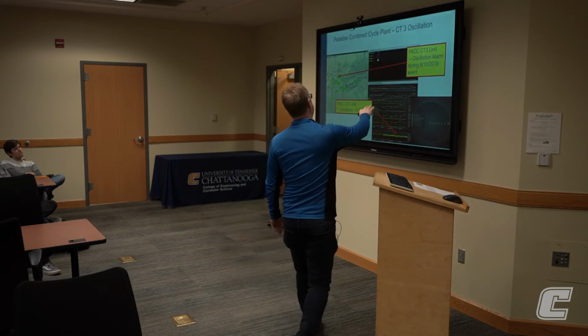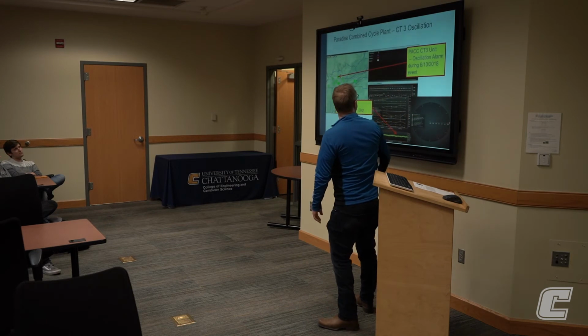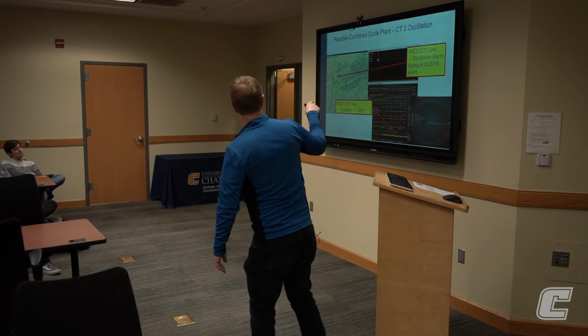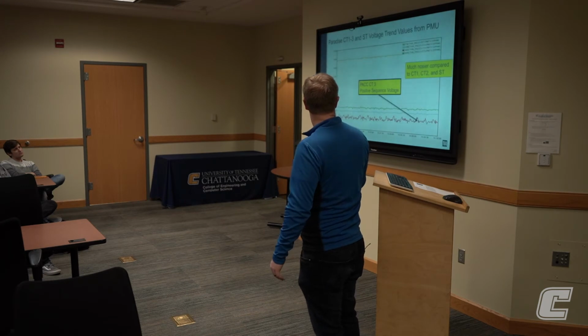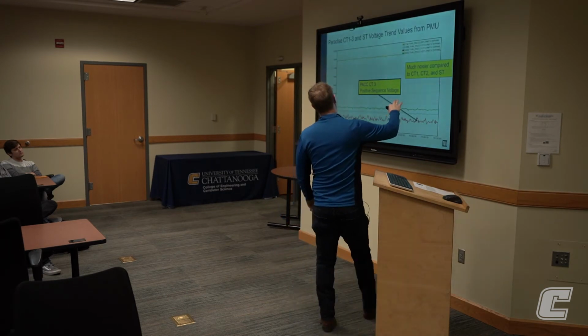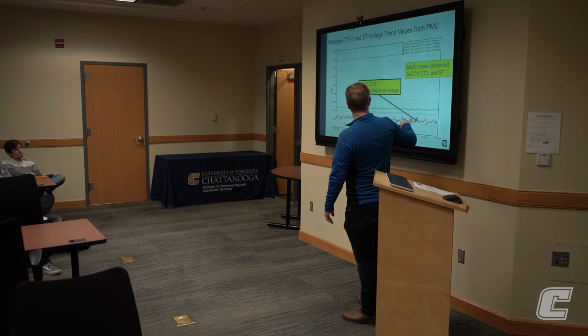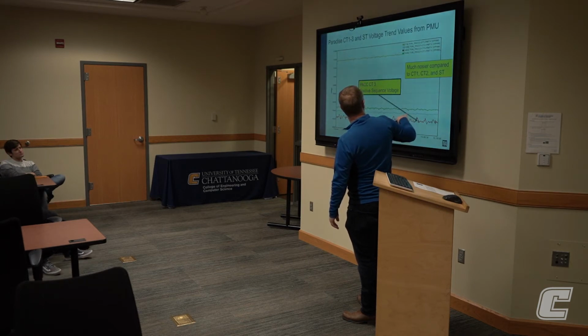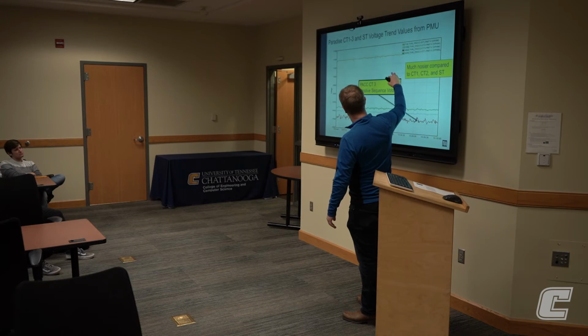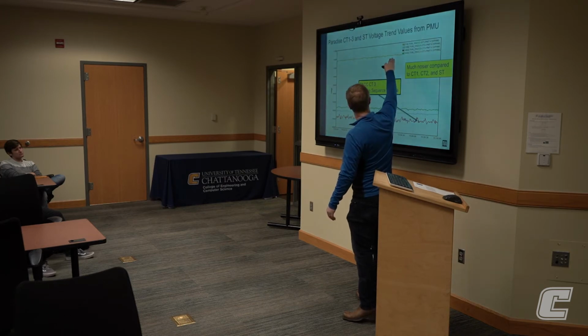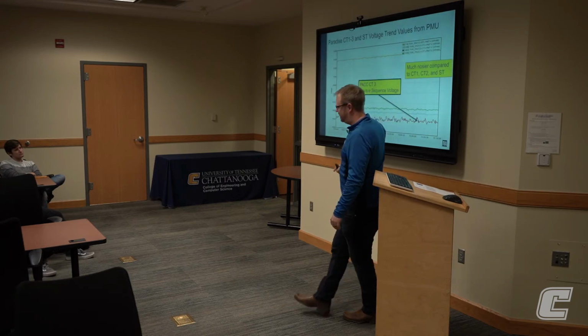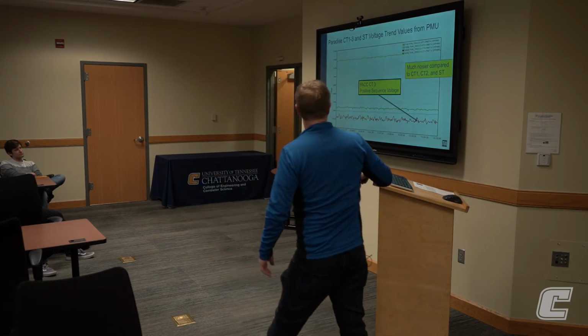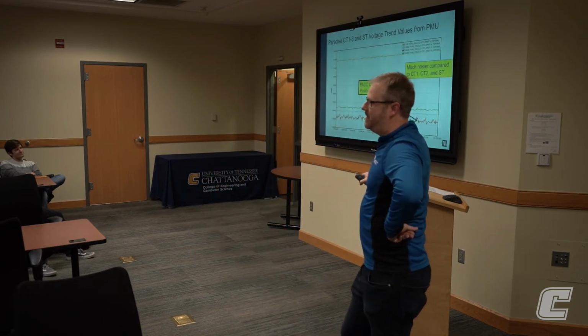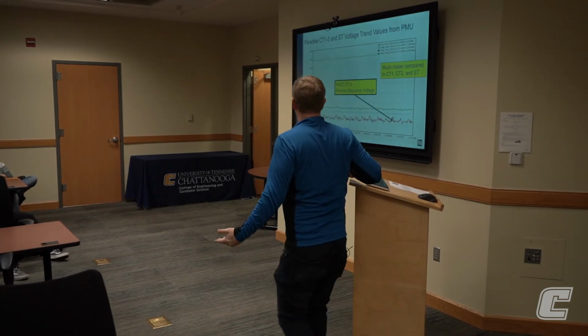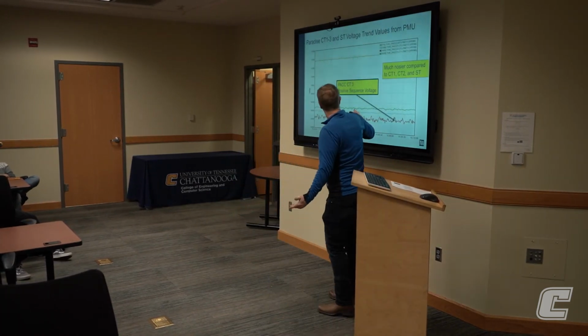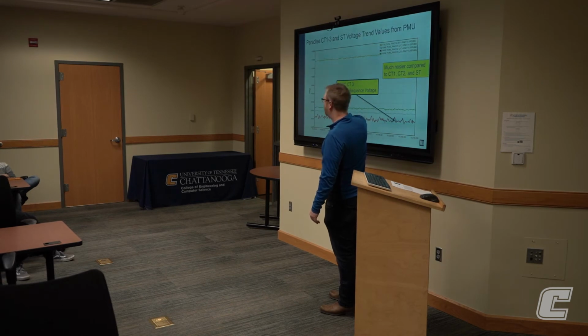So they got this alarm, Paradise CT3. You can see it was in 2018. I think this plant was commissioned in the spring. This is the actual detailed PMU data, synchrophasor data. And it's the voltage values for all 4 units. So this is the steam unit that I mentioned. These are the 3 CTs. Does one look a little different than the others? It's not drastic, but you can tell it's noisier.